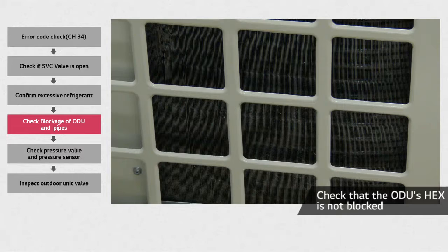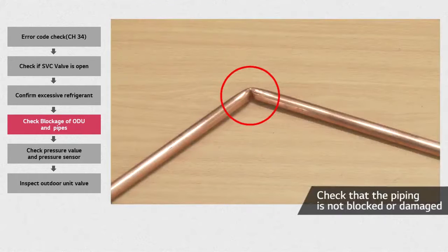Dust particles and other contaminants may block the ODU's heat exchanger. Check every side of the heat exchanger and its surroundings to make sure it is not blocked, clogged, or has any objects interfering with the airflow. Poor air circulation at the ODU's heat exchanger may also cause this error. At this point, checking the state of the pipes is also necessary. Make sure they are not blocked, damaged, or bent, as shown in the image.